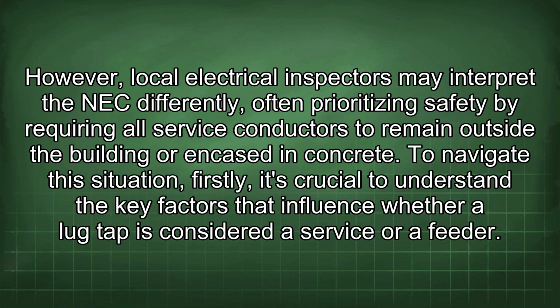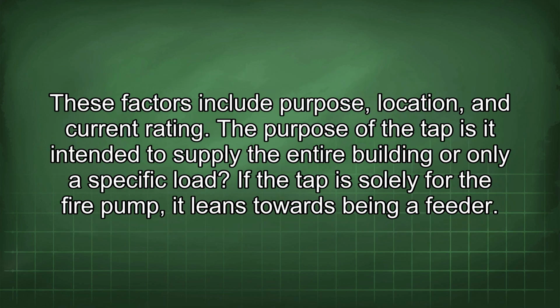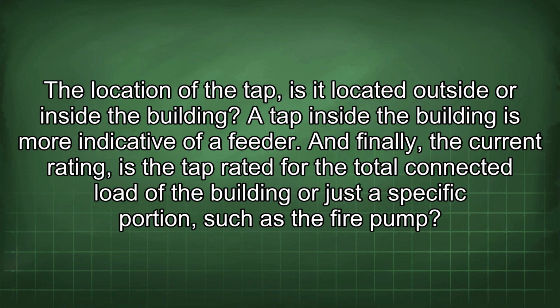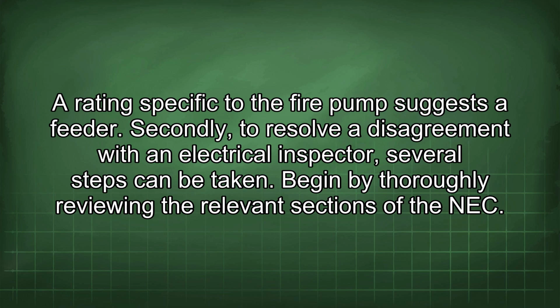To navigate this situation, firstly, it's crucial to understand the key factors that influence whether a lug tap is considered a service or a feeder. These factors include purpose, location, and current rating. The purpose of the tap: is it intended to supply the entire building or only a specific load? If the tap is solely for the fire pump, it leans towards being a feeder. The location of the tap: is it located outside or inside the building? A tap inside the building is more indicative of a feeder. And finally, the current rating: is the tap rated for the total connected load of the building or just a specific portion, such as the fire pump? A rating specific to the fire pump suggests a feeder.